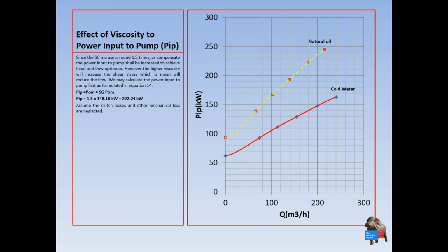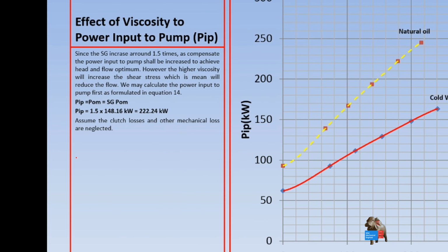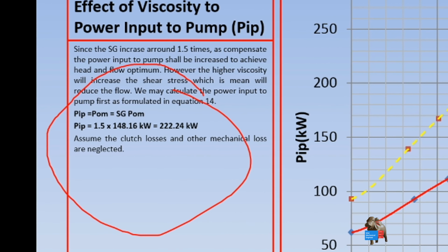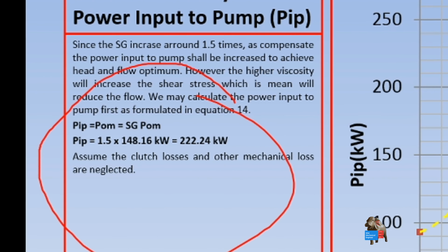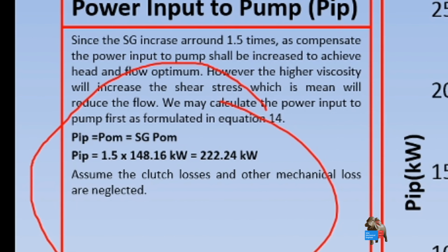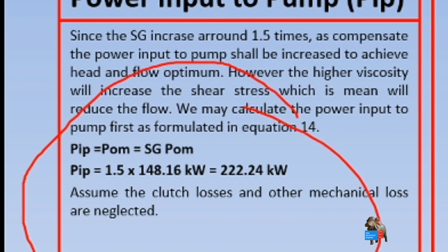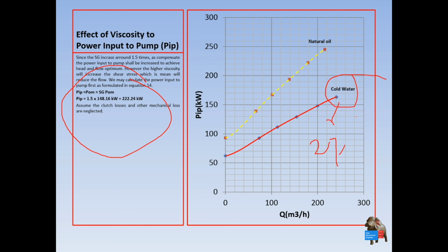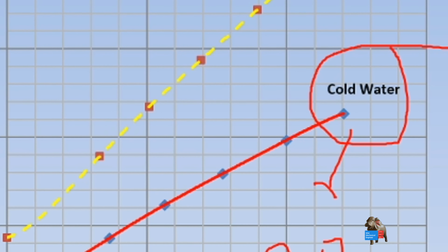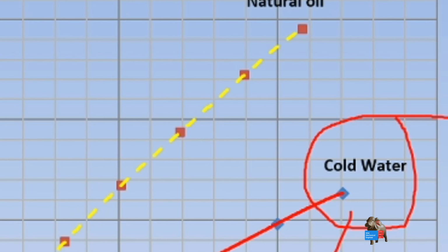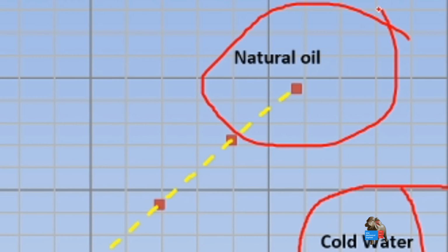Okay, and another effect is the viscosity effect on the power input to the pump. Of course, the more viscous the fluid, the more power you need. So the formula is like this. We tested the pumps with cold water at room temperature, let's say 27 degrees Celsius. But when you use the pump to transfer natural oil, which is more viscous, you need more power.